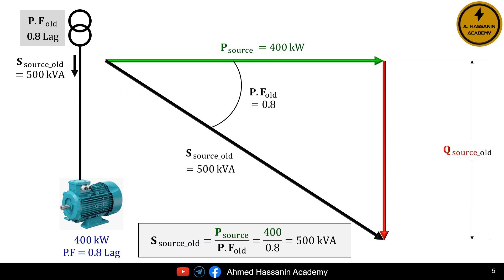So the total power of the source before installing the capacitor, that is, before improving the power factor, S source old, is equal to the active power of the source P source divided by the old power factor, which equals 400 kilowatts divided by 0.8. Thus, S source old equals 500 kilovolt amperes.